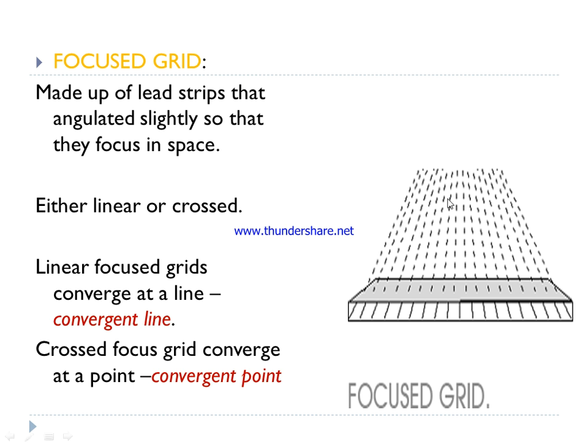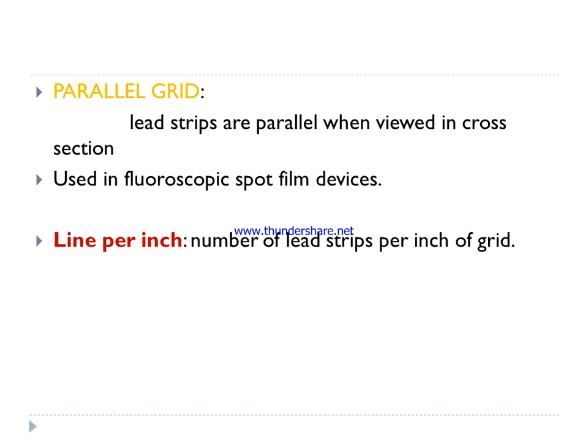In a focus grid, the lead strips are angulated slightly so that they converge toward a focal point or line. This makes the grid focused. In the case of a linear focus grid, the strips converge at a line called the convergent line. For a cross focus grid, convergence occurs at a point called the convergent point.